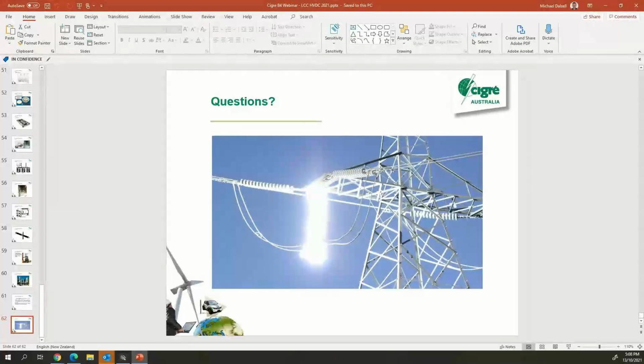Yeah, and with the New Zealand link, how many extended commutation failures have you had, and do you think you'll have more as more IBR connects, or do you have enough synchronous generation that you think it will be okay? Yes, there is a bit of an issue with the New Zealand system, and that is there's not a lot of generation in the lower North Island where the link terminates. We're at Haywards, where I'm sitting now. We're pretty much operating as an inverter about 70% of the time, as I said.